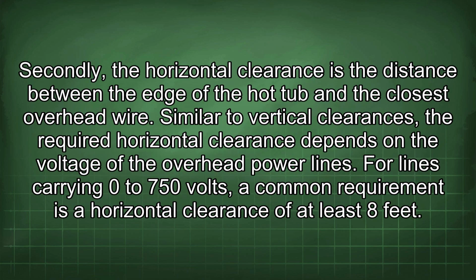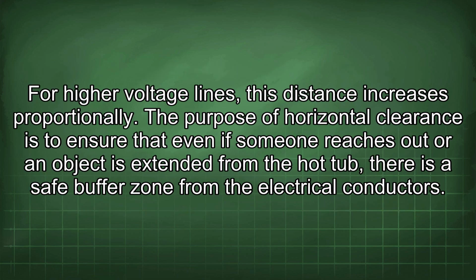Secondly, the horizontal clearance is the distance between the edge of the hot tub and the closest overhead wire. Similar to vertical clearances, the required horizontal clearance depends on the voltage of the overhead power lines. For lines carrying 0 to 750 volts, a common requirement is a horizontal clearance of at least 8 feet. For higher voltage lines, this distance increases proportionally. The purpose of horizontal clearance is to ensure that even if someone reaches out or an object is extended from the hot tub, there is a safe buffer zone from the electrical conductors.